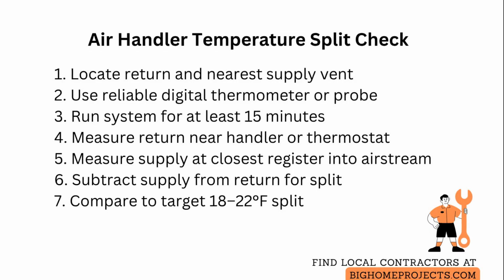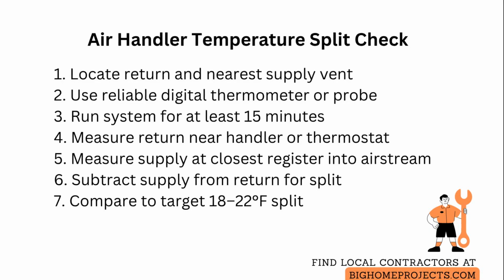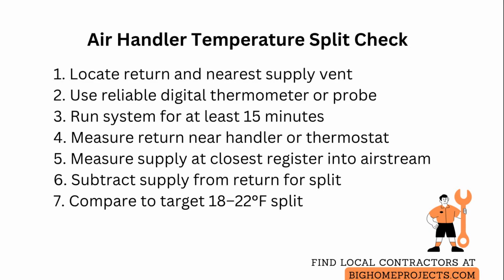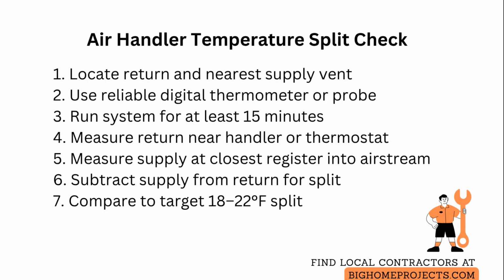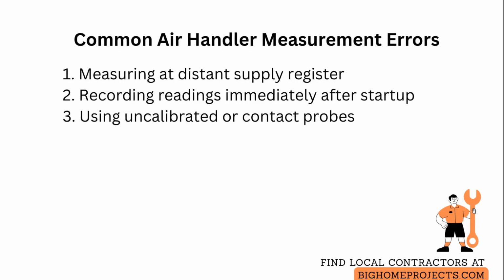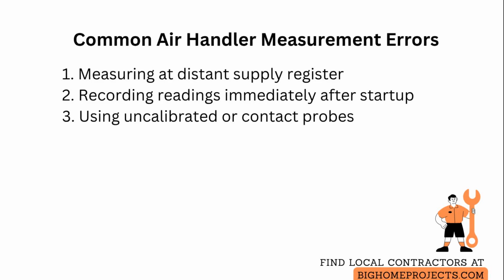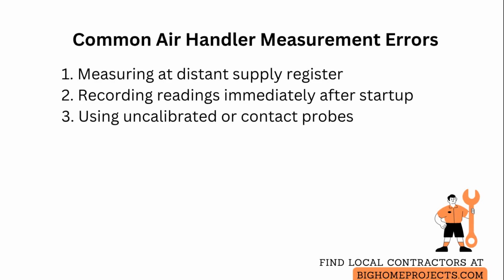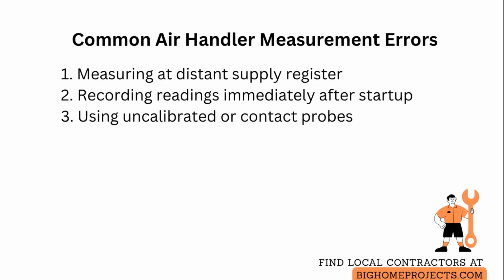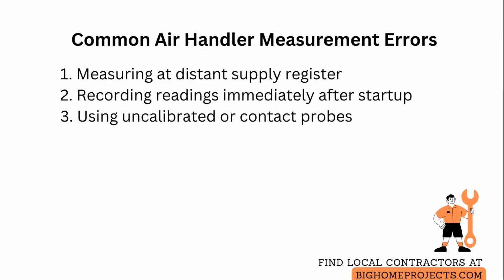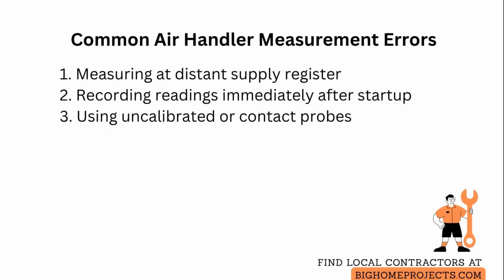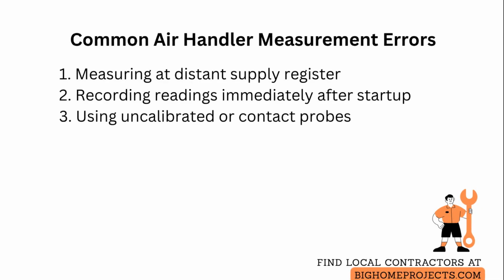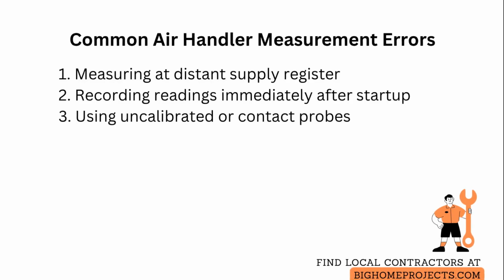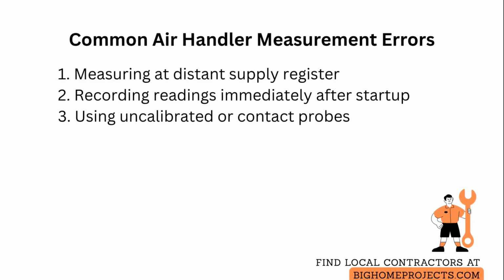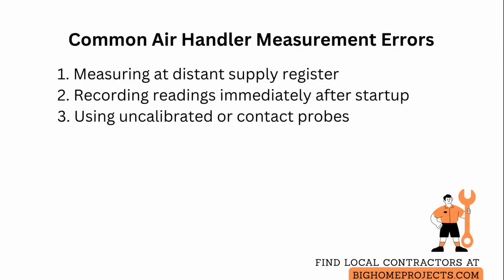If the system is humidifying or defrosting, account for those conditions because they will alter sensible cooling and the apparent split. Common mistakes include measuring at a distant register, which gives misleading high splits, so always use the supply closest to the handler and the return nearest the thermostat. Another frequent issue is taking readings immediately after startup, which gives transient values, so run the system for at least 15 minutes before recording temperatures.